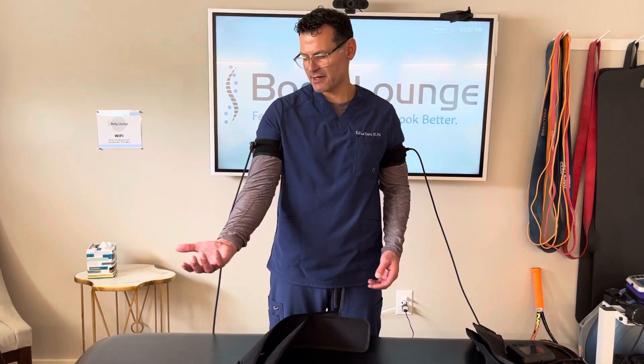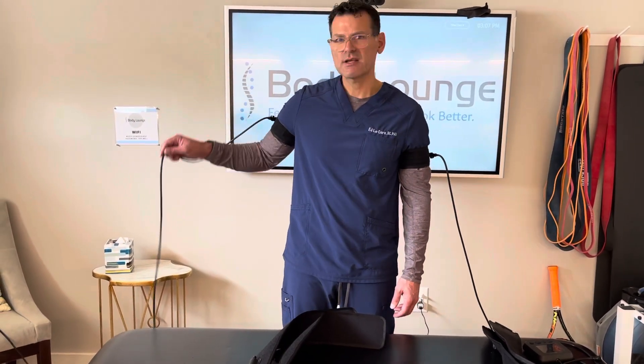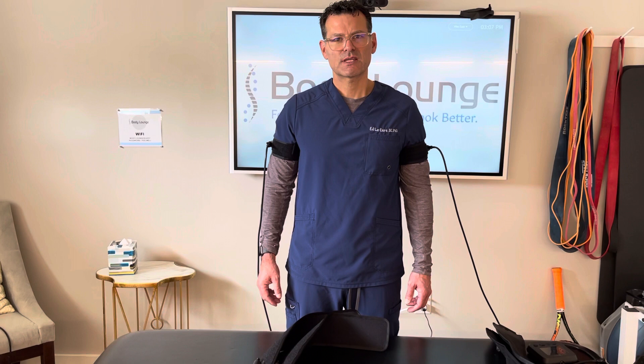If I don't want to auto regulate, that's okay. You can just disconnect the hoses prior to choosing auto regulation and exercise without the cuffs — which I would want to do if I'm outside, have a lot of equipment around me, or don't want to be tethered by the cords. So that's how to do upper extremity using the pro pump generation 3 smart tool, smart cuffs.